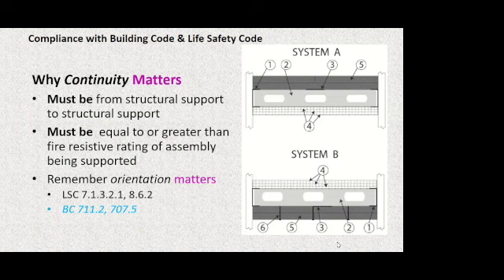And when the design that was tested by the test lab says it must be supported by a 2-hour wall on each side, you can't just get rid of the walls. And the reason for that is pretty simple, because the walls were tested under that simple compression where they retain most of that compressive strength residually at fire temperatures. But when we lop off the bottom of those walls and we create these U-shaped boxes, what we're doing is taking the same lightweight framing and putting it under tension.